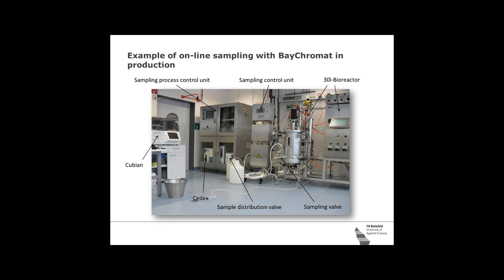Here, this is for a 30-liter stainless steel bioreactor. And this is an instrument or a device that takes samples from such a bioreactor, from BTS, Biotechnology Services. They developed a valve here, which can be implemented into the bioreactor. It can be steam sterilized. That's important because no chemical disinfection or whatever is acceptable to the customer. It needs to be steam sterilized because that's also the standard procedure. And this little tower here, that's the sampling control unit that is next to every bioreactor that is being sampled.